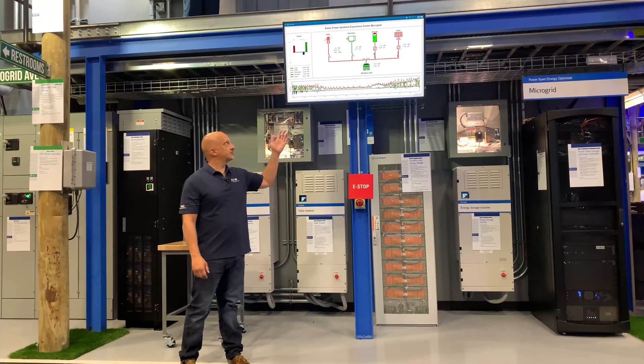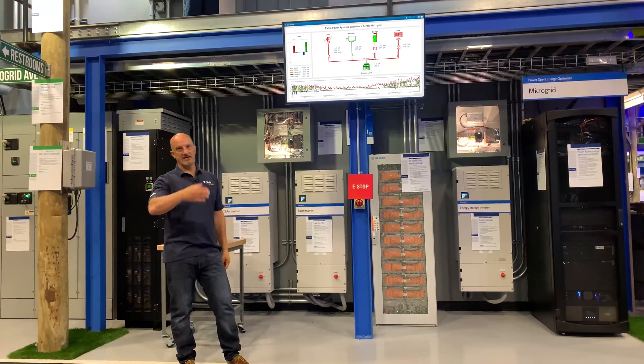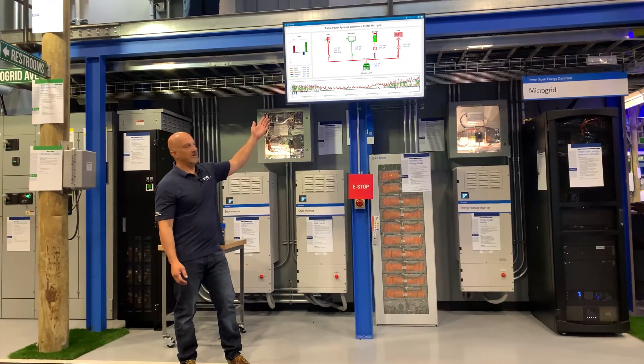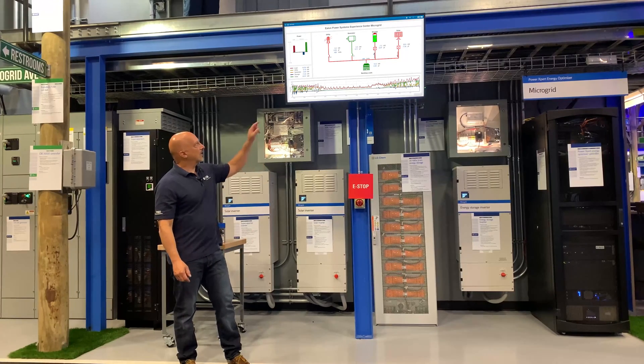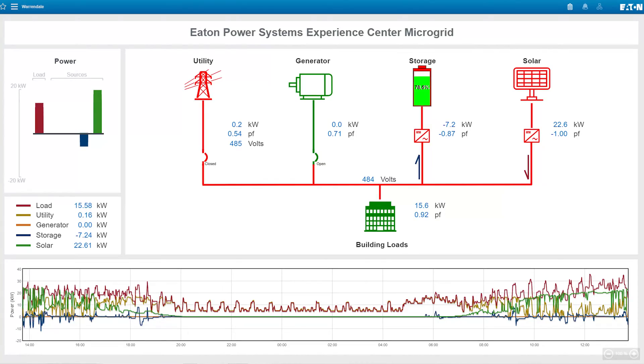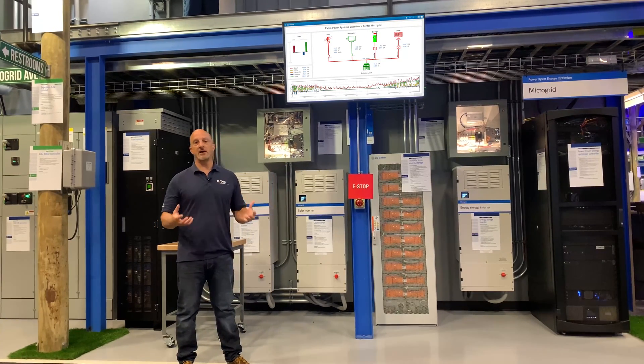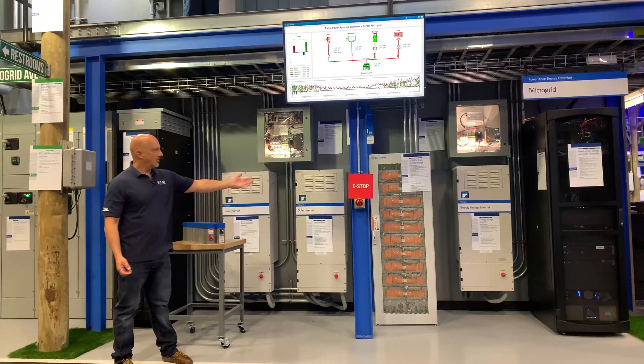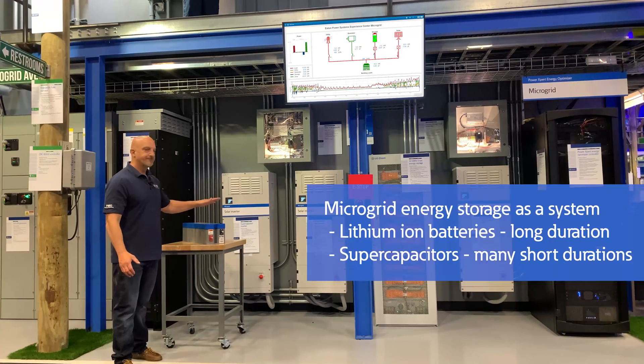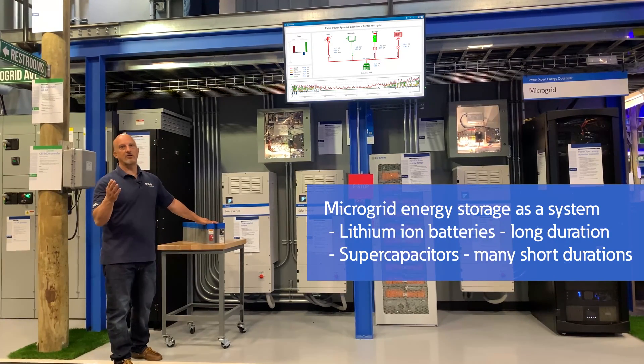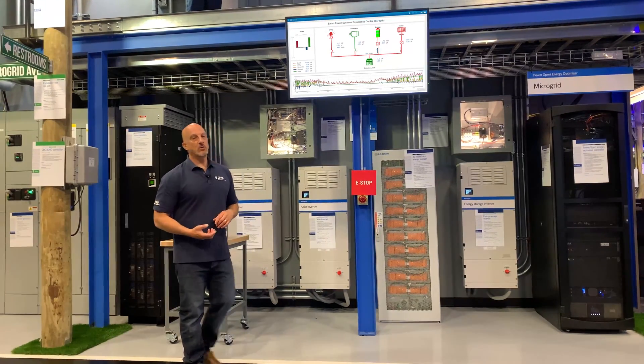On a smooth sunny day we have good solar all day long, but today we have this jagged green line. Where does energy storage come in? The blue line shows the response to that jagged solar — right now we're actually charging the batteries because we have a lot of solar, but in another situation we would discharge the batteries because the solar goes behind a cloud. It's a great concept and a good way to use a microgrid as a system to optimize your storage, especially with lithium ion batteries and supercaps for those short cloud-passing events.